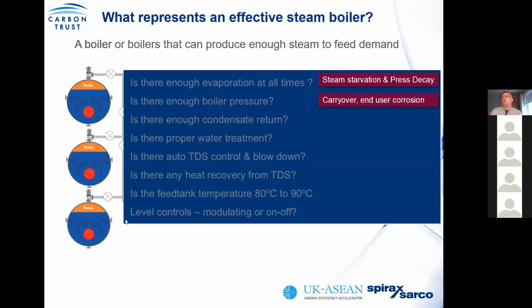You also need to understand, is there enough condensate return? So we will demonstrate why you should be returning condensate, the financial benefit. But it's not just a case of how it's returned, but how it's brought into the system and how it interacts with your makeup water system and your boilers. Is there proper water treatment? What we have found from experience is that a lot of the problems in steam systems is a misunderstanding of the water treatment regime, the impacts it has on the quality of water in the boiler, and effectively, if it's not controlled, it can impact even simple things like boiler level controls. And if you've ineffective level control, then you've an inefficient boiler system. However, on a steam distribution system, where there's ineffective treatment, where there's carryover, you end up with corrosion and even blockages of some end users, because you end up bringing particles into the steam distribution system.